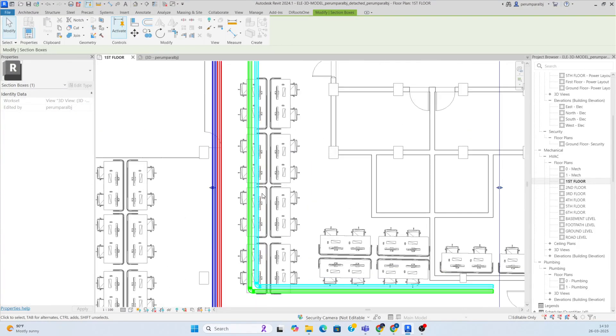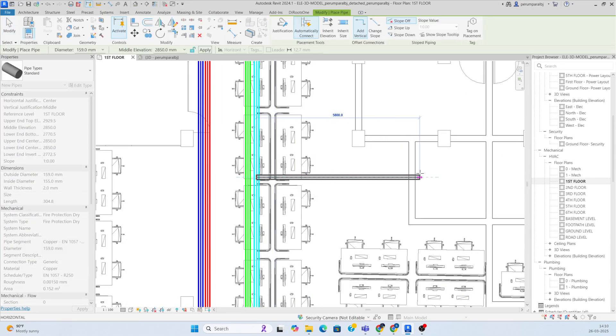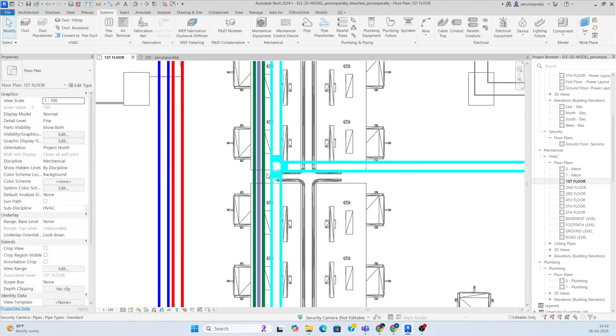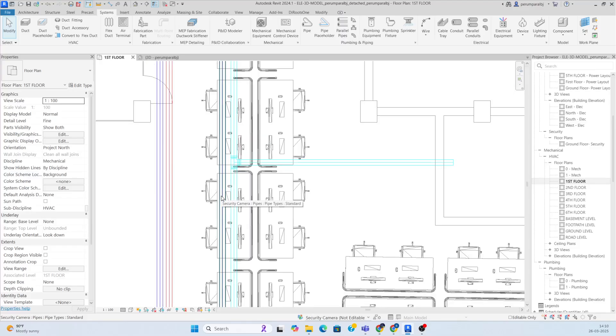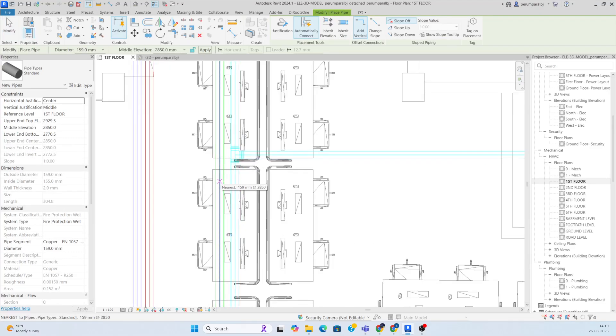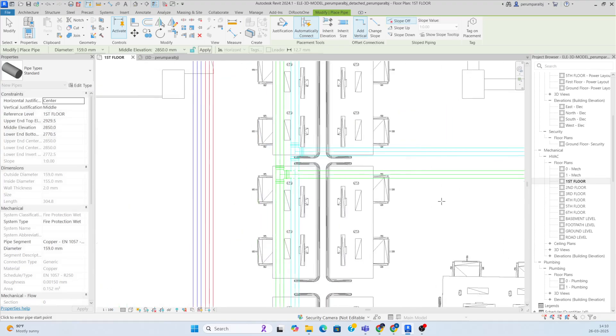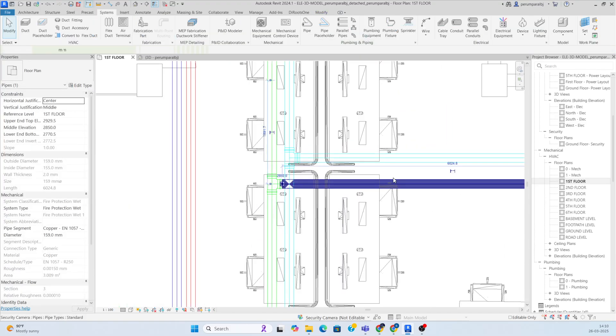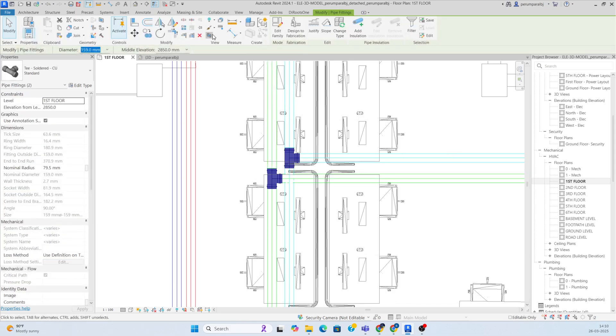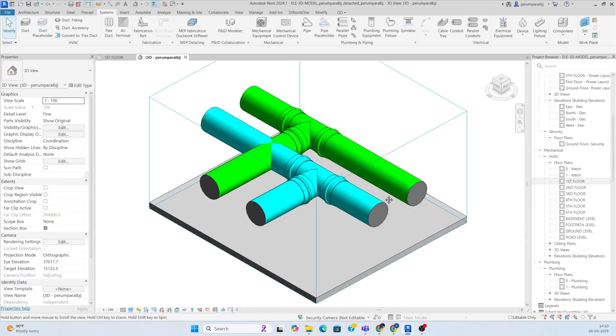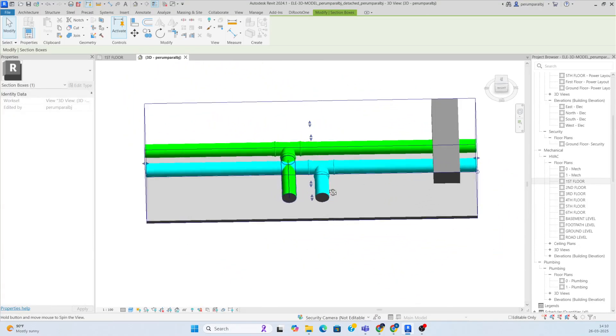Now draw branches for this pipe. Use 'create similar' and draw the branch pipe up to the required location — the fitting will be taken automatically. However, making a branch here will clash with another pipe. If you look in the 3D view, you can see the pipes are clashing with each other, so you need to adjust the height of one of the pipes.